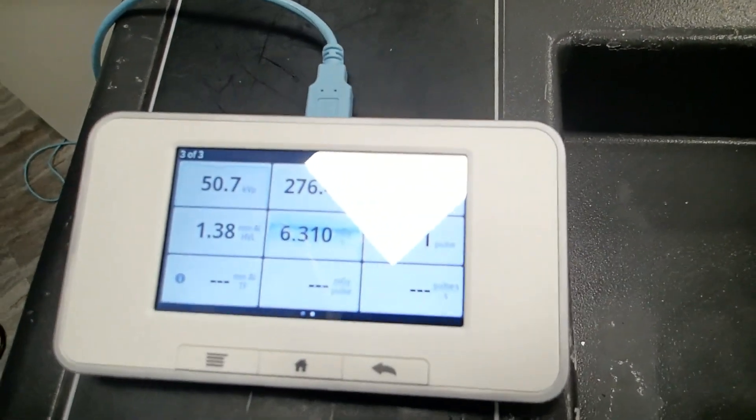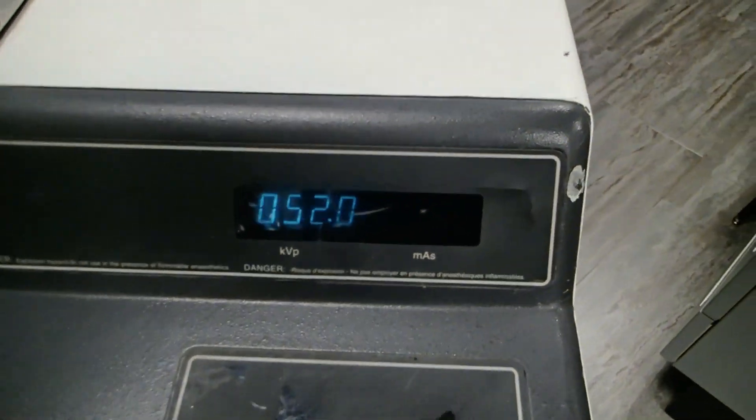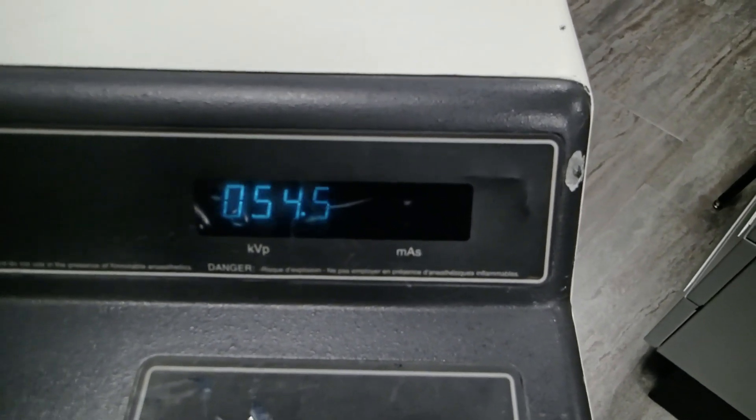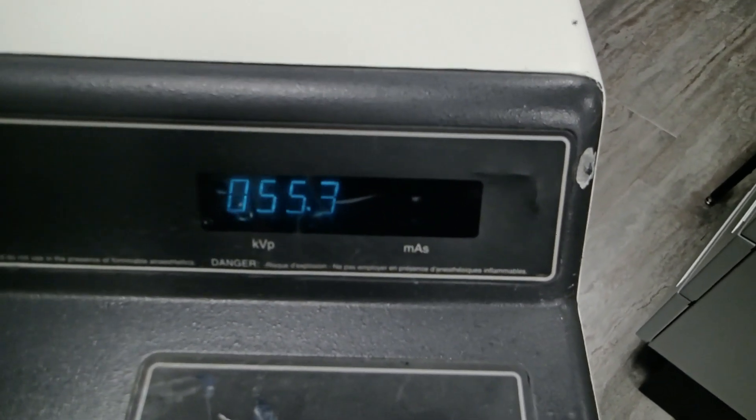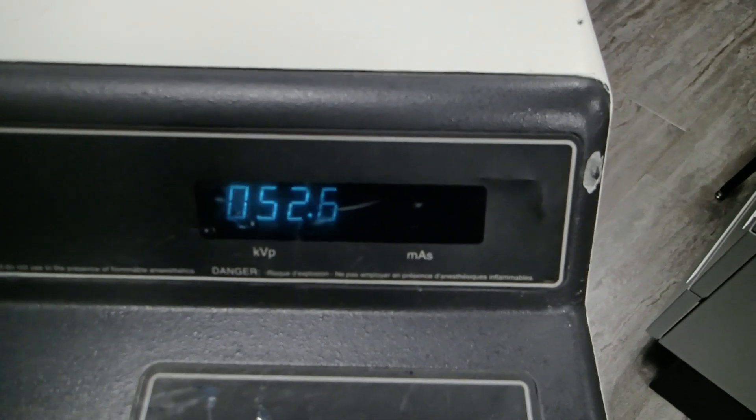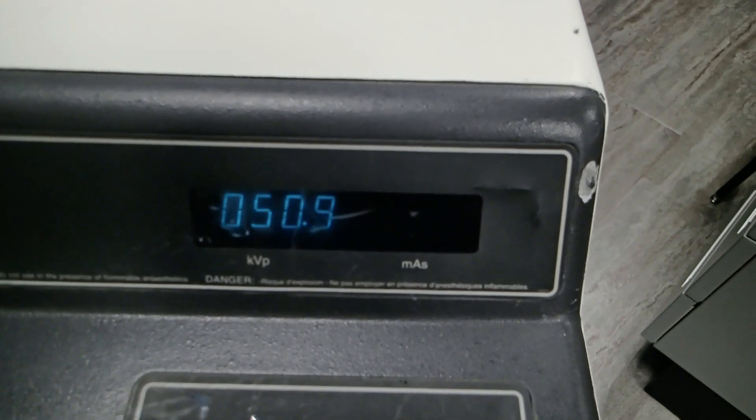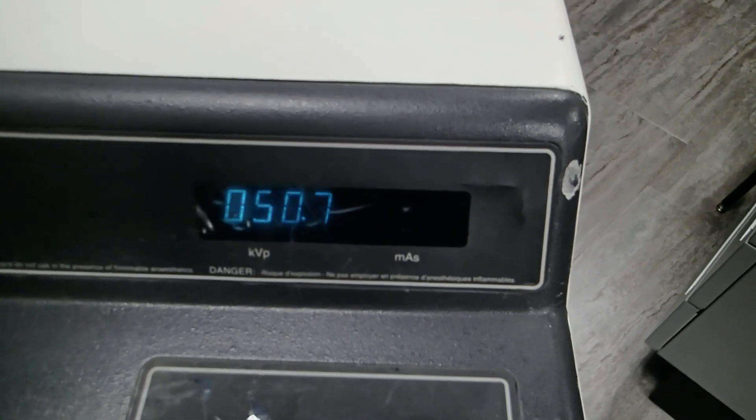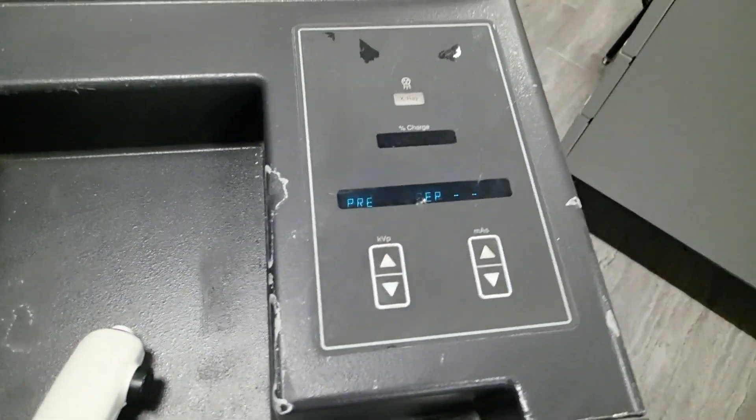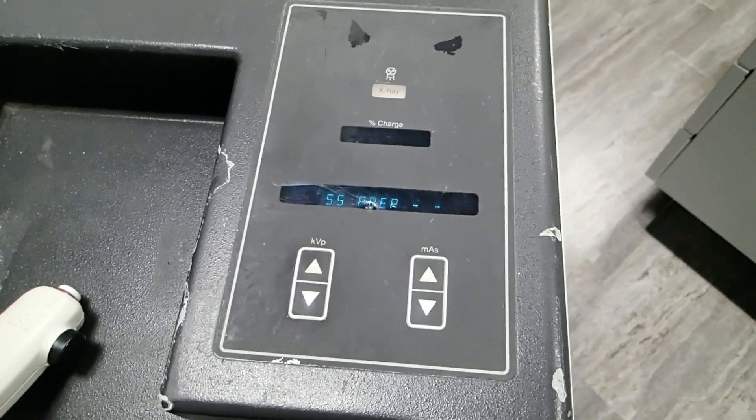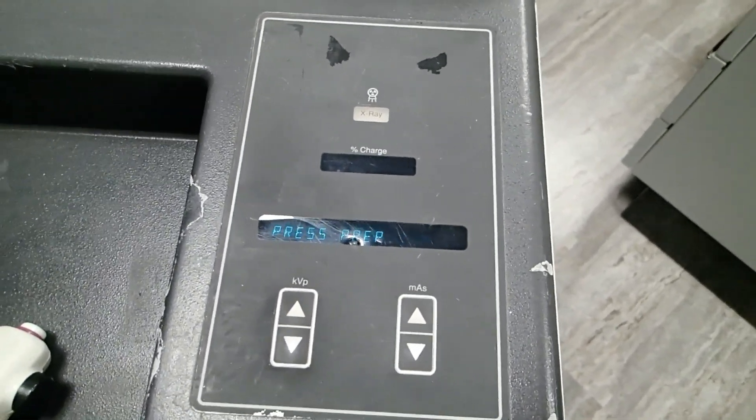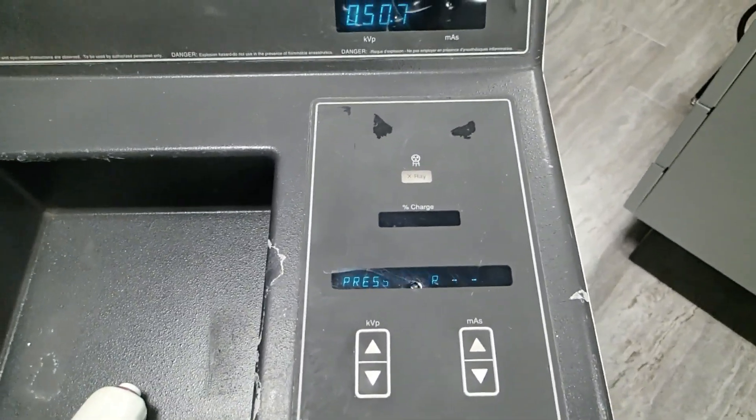We're being asked to enter value 50.7. Once again, we've got to change that. 50.7. And then enter that value. Now you can continue to go through this process. It's an iterative process. We're going to go through that at different levels of KVP until you're done.